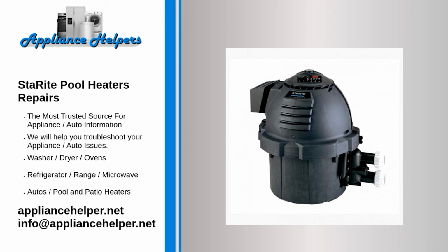Gas pool heater cycles on and off frequently. Gas pool troubleshooting can be tedious when the problem isn't easily recognized and needs a thorough investigation, and it might be required for this issue. If the cycling on and off is accompanied by loud banging noises, then be sure to read "heater is making loud noises" below. Inadequate water flow or malfunctioning pressure sensor.